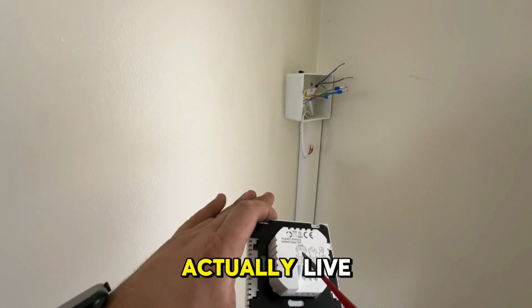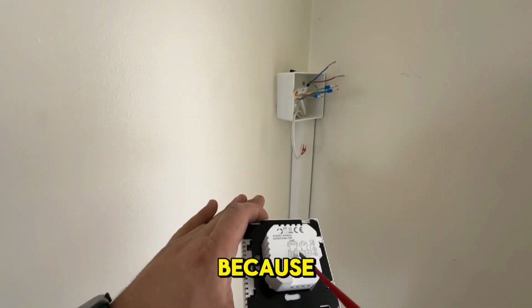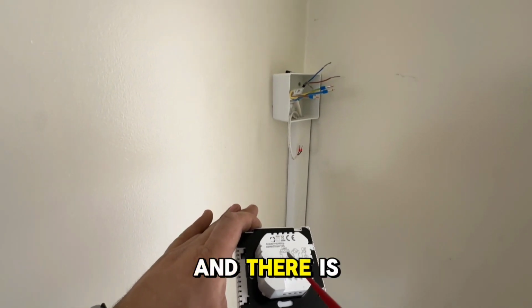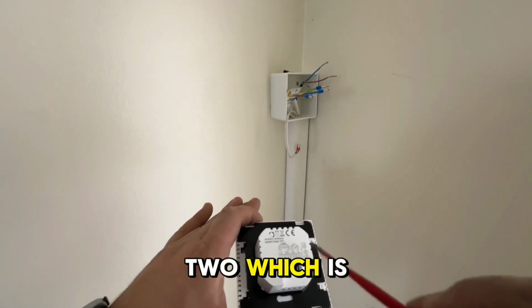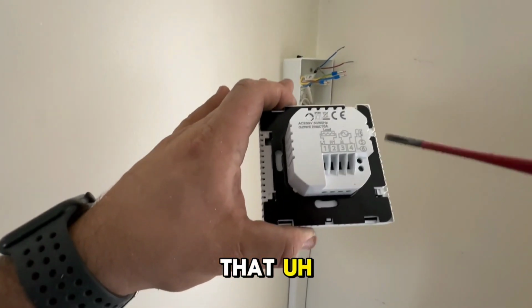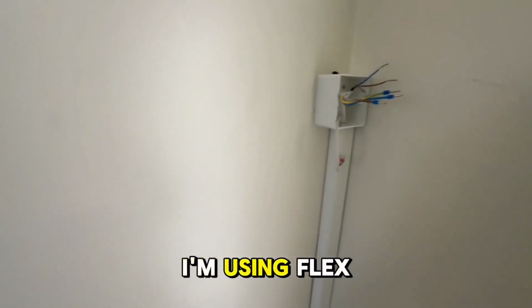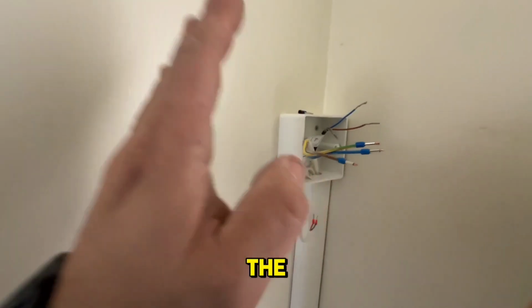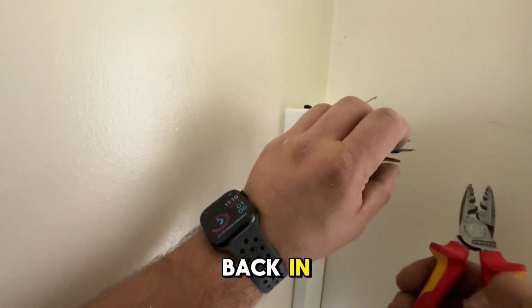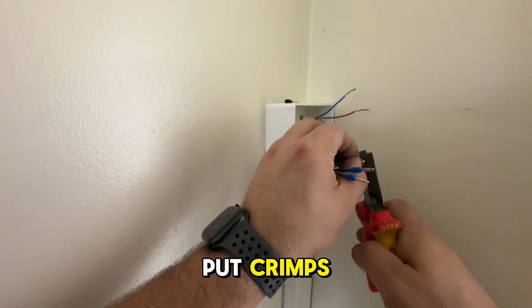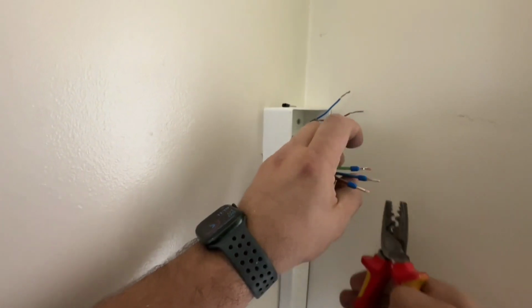And you've got actually line, neutral, neutral, line, because neutrals are just linked, and there is a switch between these two, which is operated by that floor probe. Let's do it. I'm using flex because it's just easy to push the whole thing back in, and I always put crimps, ferrules on the end.